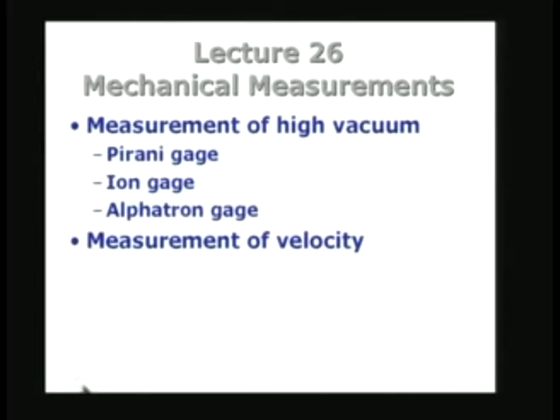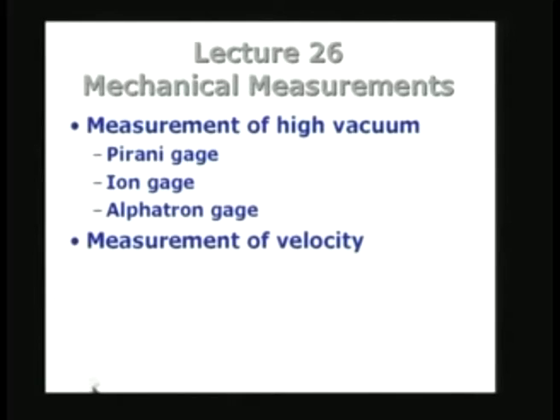Let us look at the measurement of high vacuum. The Pirani gauge principle is very simple. If you have an electrically heated element, the amount of heat transferred from that element is related to the speed with which it can be carried away by the surrounding fluid. As the surrounding fluid pressure reduces, the amount of heat it can take away also reduces. Therefore, if you heat an element in the presence of background vacuum pressure, as the pressure reduces, the temperature of the element will increase.